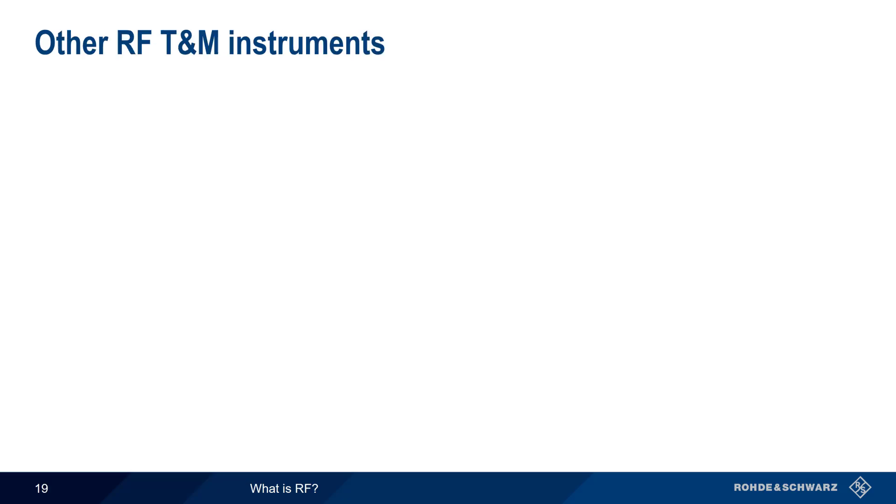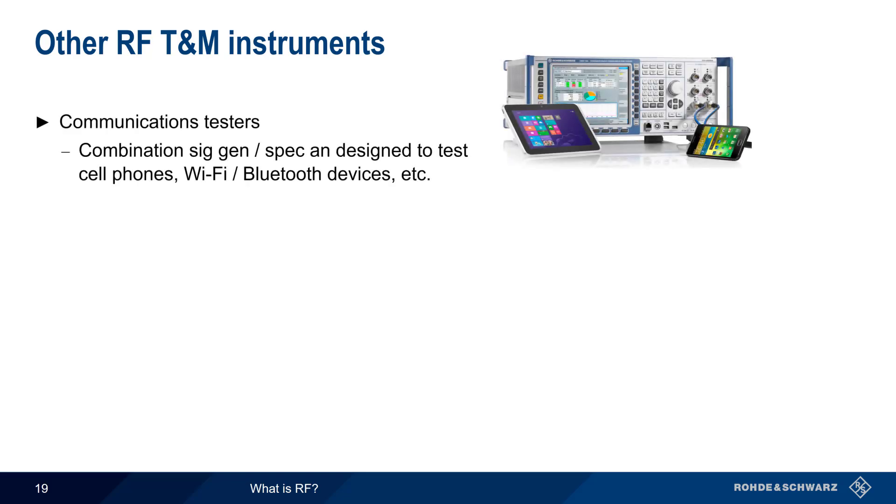In addition to the four categories we mentioned earlier, there are many other types of RF test and measurement instruments. Communications testers are something of a combination of a signal generator and a spectrum or signal analyzer. These testers can emulate a wireless device, a wireless access point, or a cellular base station, and allow both voice and data testing.